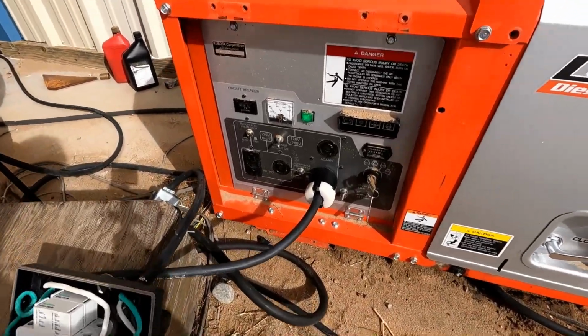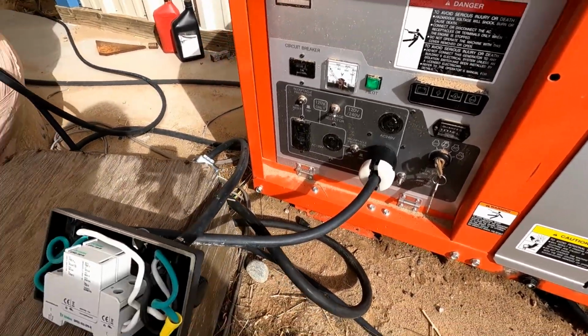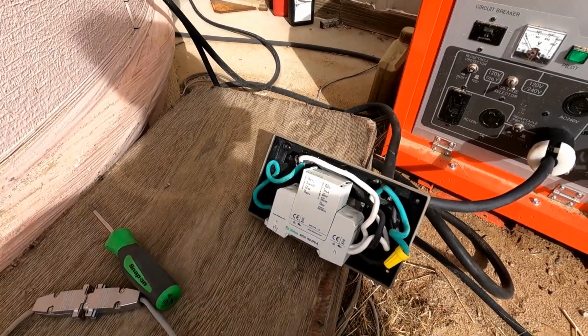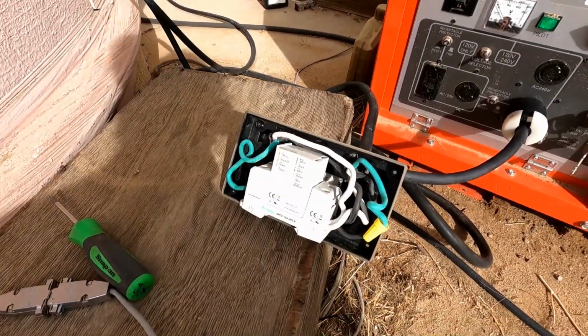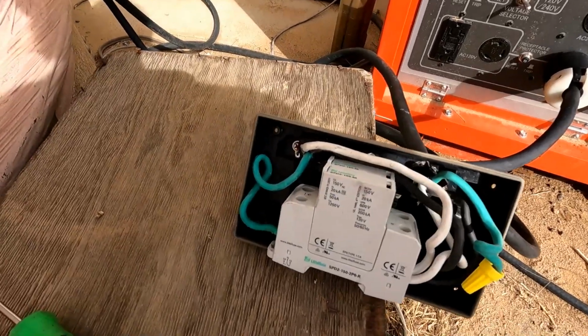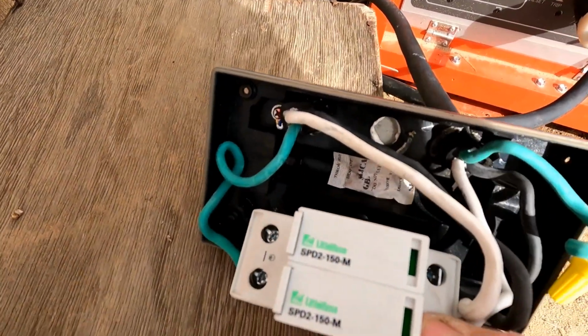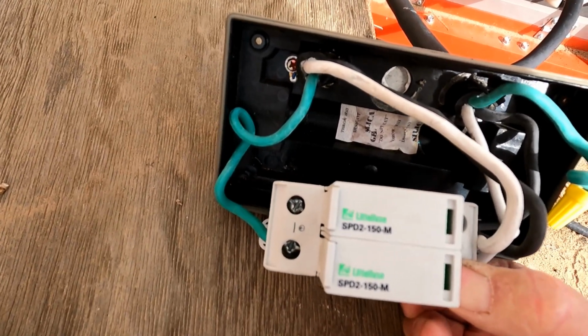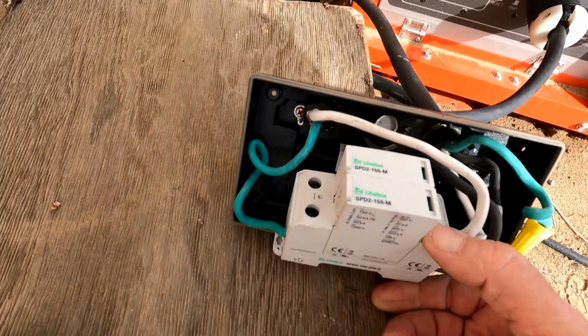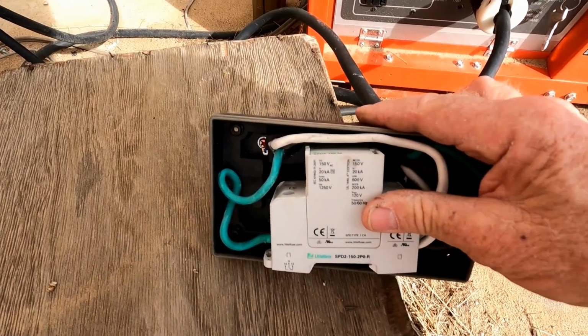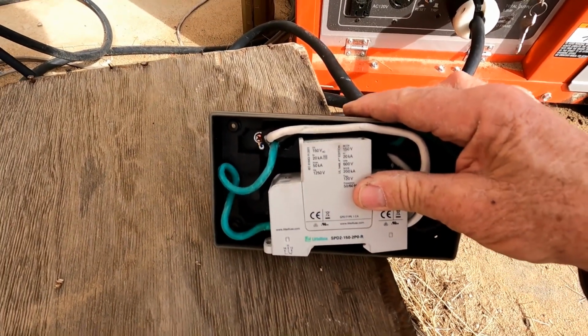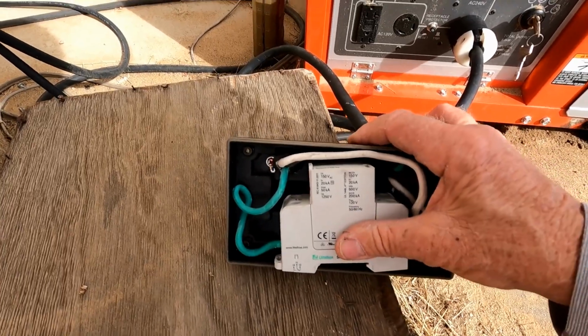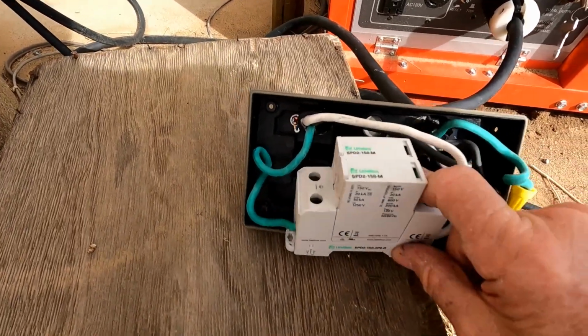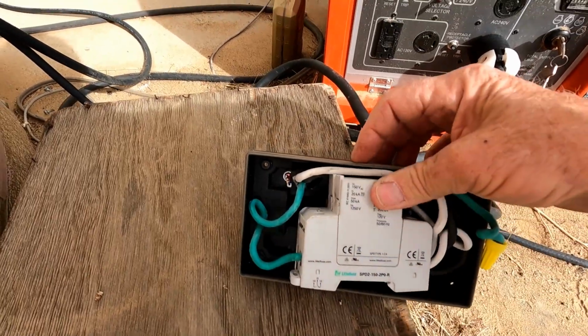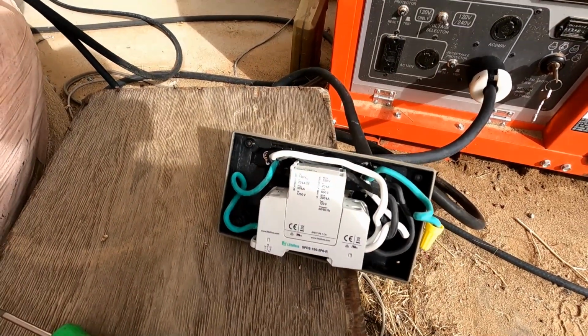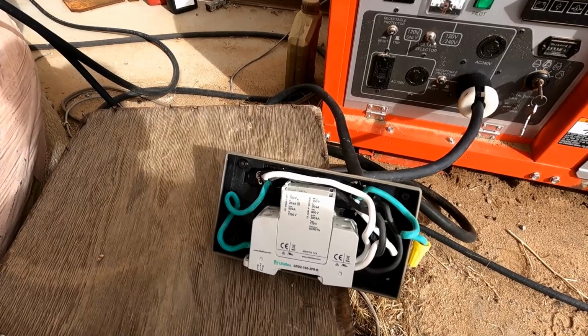And of course, we're all very familiar with surge protection. However, in this case, you don't want to go to Home Depot or Best Buy for your surge protector. What you need is a real heavy-duty industrial grade surge protector like this Littelfuse. It's a dual SPD2-150M. And these are 150 volt industrial grade circuit breakers rated for 20 kiloamps of transient absorption. And this is actually sold in a pair. There's an extension on the part number. I'll give information on where I got this from DigiKey for about $125.